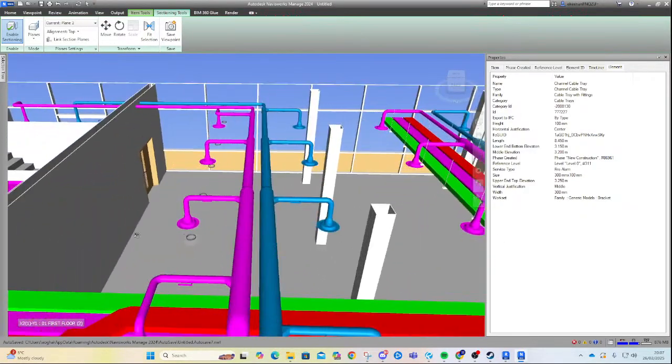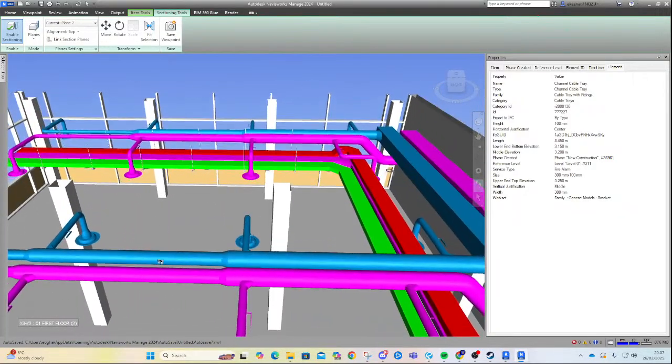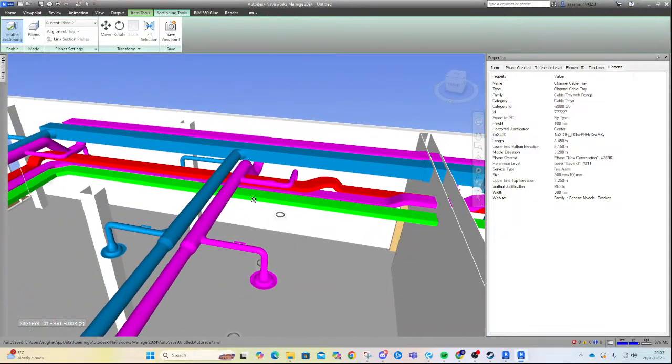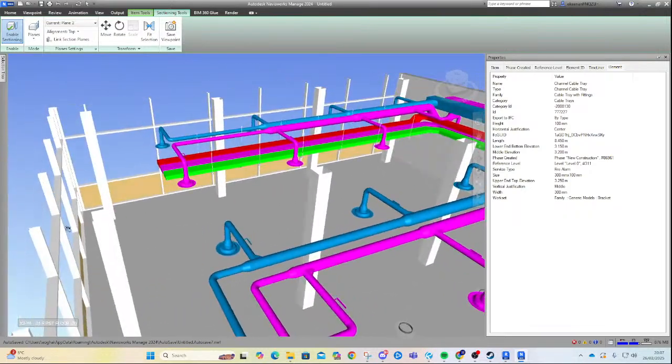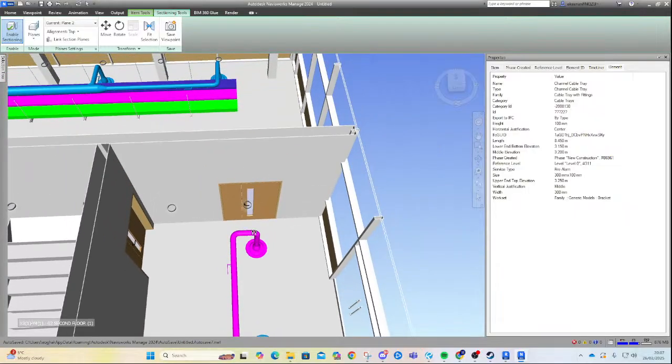Should we be following the ductwork? Should we have a branch over here? How are we going to get from here to these lights, for example? So we should have another one, coming down here servicing these lights, because we're obviously going to have lights and smoke heads in that room. We've nothing in here, so it's easy to see in areas.